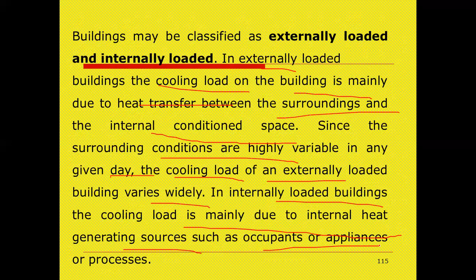Since the surrounding conditions are highly variable in any given day, the cooling load of externally loaded buildings varies widely. In internally loaded buildings, the cooling load is mainly due to the internal heat generating sources such as occupants, appliances or processes. So generally, the heat generation is due to what? Due to the internal heat being fairly constant, and since the heat transfer from the variable surroundings is much less compared to the internal heat sources, the cooling load of internally loaded buildings remains fairly constant.